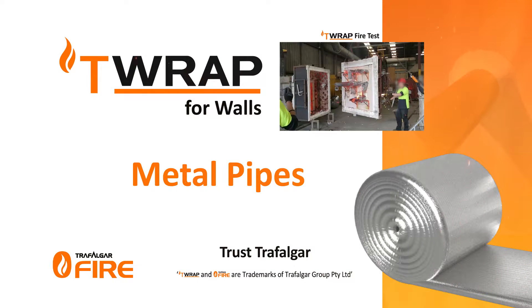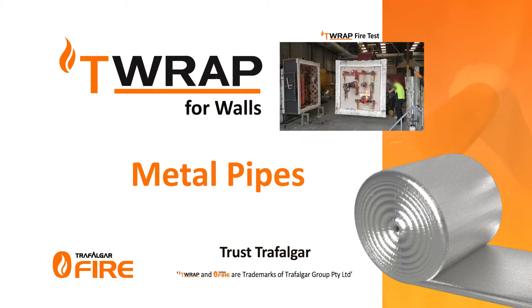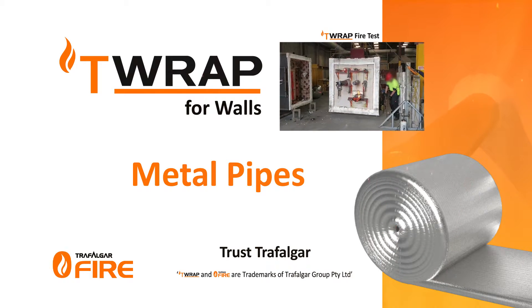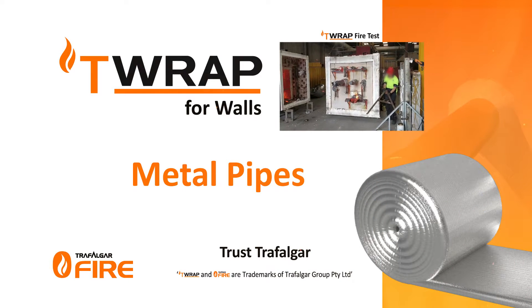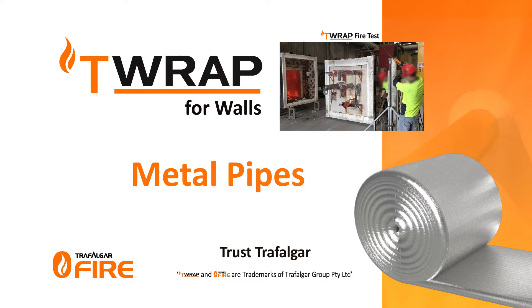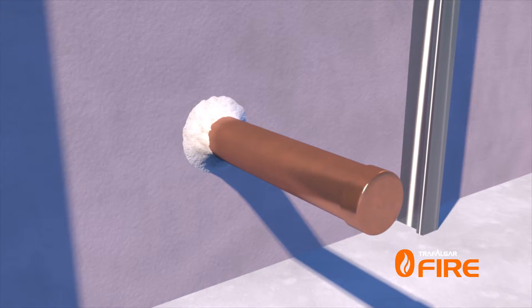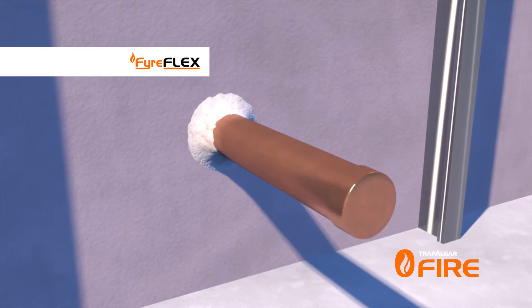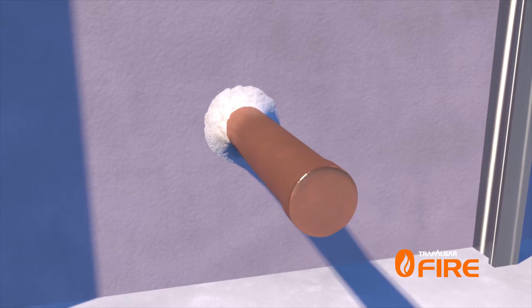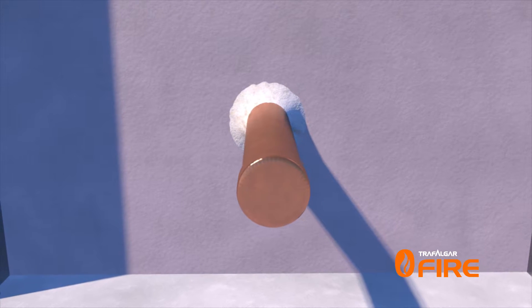Installation of T-Wrap and FireWrap is fast, clean and easy due to the fully encapsulated wrap material and simple installation steps. The installation must be installed as required for integrity performance using Trafalgar's range of fire stopping systems. In this installation video, the penetration has been sealed with FyreFlex sealant to provide two hours of integrity performance. However, as the metal pipe will transmit heat through the penetration, it will need to be wrapped to limit the heat rise.